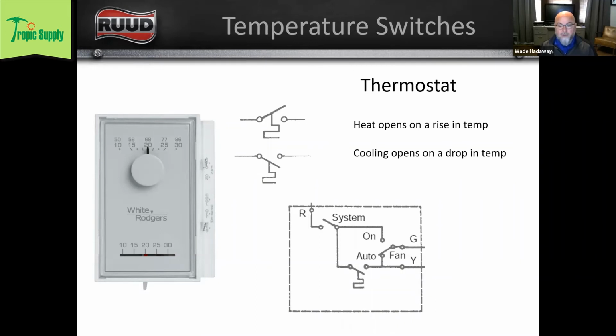Our thermostatic switch, as the temperature rises, we're going to push that switch closed, and we're going to energize Y and G. Now, if we had the fan turned from auto to on, right there where it says fan auto on in the diagram, we would flip that switch up so that as long as the system is on, either heating or cooling, we're going to energize the fan. Currently, the way it's set up is that we only get voltage to G when we have a call for Y, meaning that as the temperature rises, we push up on that switch, it closes, and then you can see we've got parallel circuits going to Y and G to our air handler and our outdoor unit, or our indoor unit and outdoor unit, I should say.